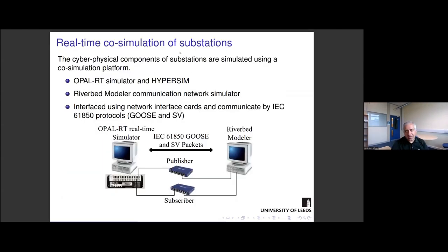In the scenarios that we tested, we used a real-time co-simulator based on OPAL-RT and HyperSim, which we used to model the physical part of power systems. Then we also had Riverbed Modeler for communication network simulation. And finally, as you can see in the figure, we interface these two simulators based on network interface cards and communicate by IEC 61850 protocols, basically GOOSE and SV, which are two very important protocols in substations for power systems.